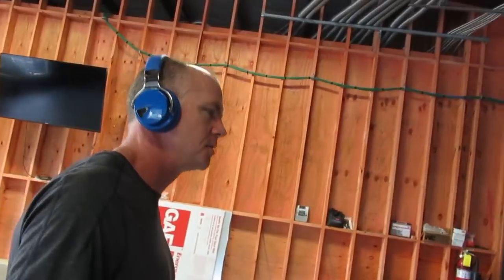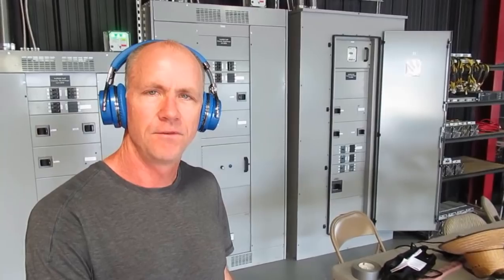Now you can see over on the side here we have 4 1200 amp panels. They look a little bit different. Not really sure why Siemens delivered different panels, but sometimes that happens, I guess. Each 1200 amp panel has a service disconnect that goes outside, and it can trip everything all at once in case there's a fire. Then since it's three-phase, the rotating machinery goes directly off these three-phase panels, and they also feed 400 amp sub-panels where we peel individual phases off. You'll see inside that there's a number of 30 amp, 208 volt receptacles that we plug PDUs into and then plug miners into.